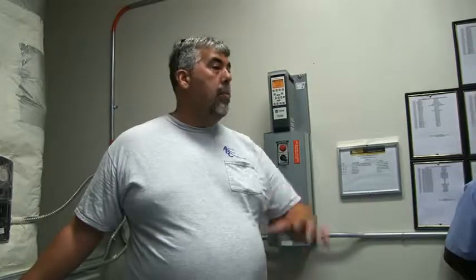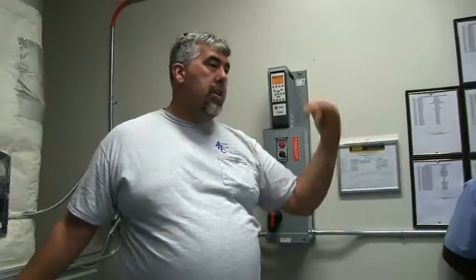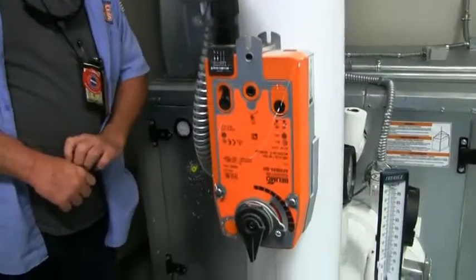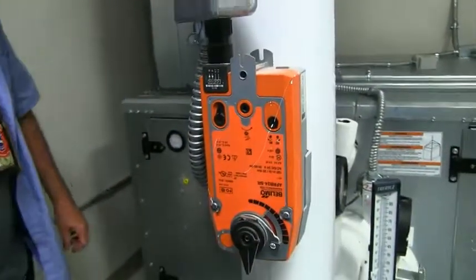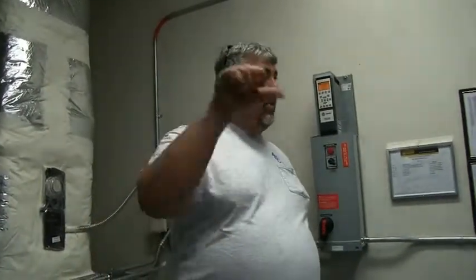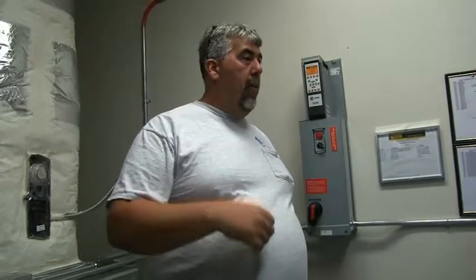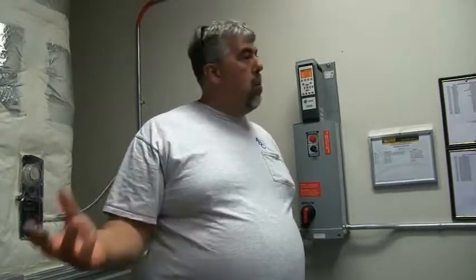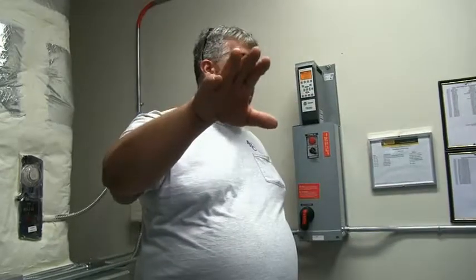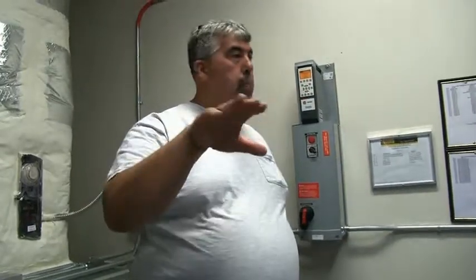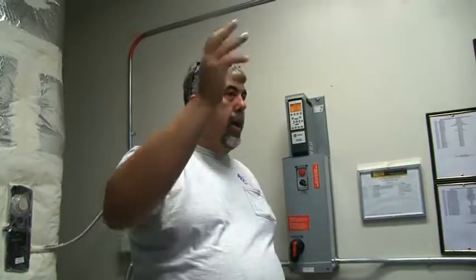When this thing goes into dehum, because there's a dehum sensor out here in the hall, when it sees the humidity get above, I believe it's 60%, it's going to put the unit in dehumidification mode, at which time this valve is going to open 100%, and it's going to allow the temperature of this coil to drop as low as it needs to. Now there's a plus or minus differential for that humidity. Once it drops by 5 from the set point, it will kick out of dehum mode and go back to working the way it was supposed to. It'll go back to its nominal set point and start resetting up or down based on box positions and temperatures.